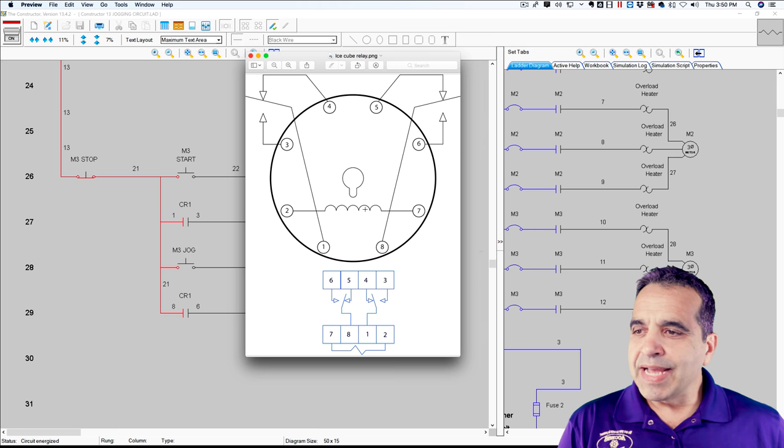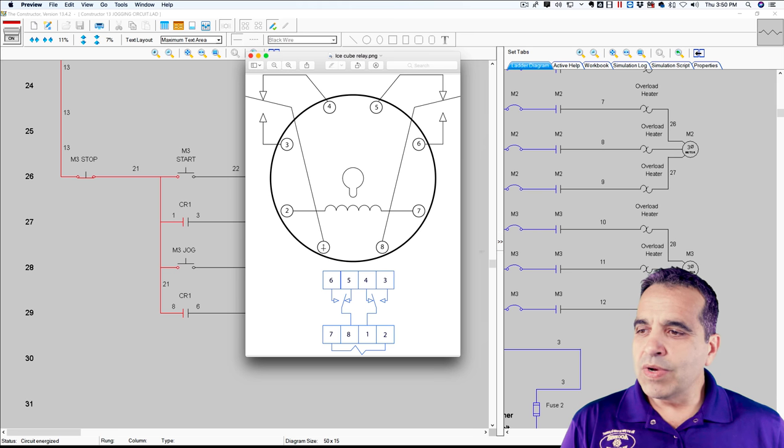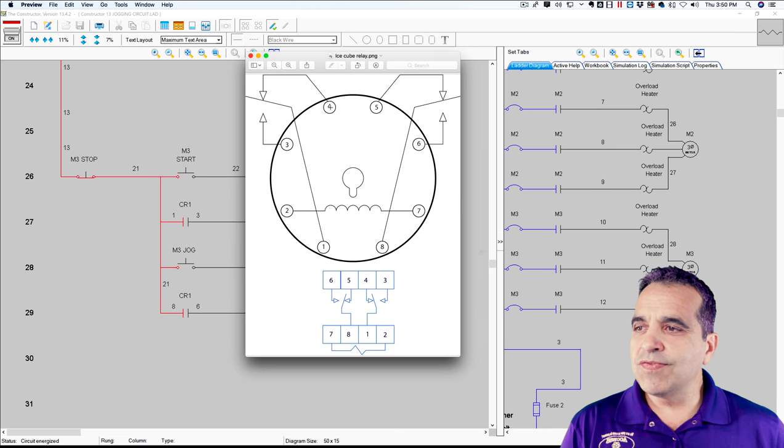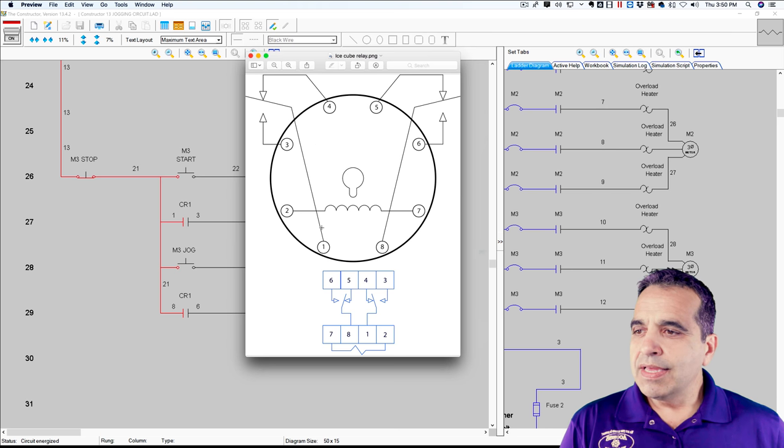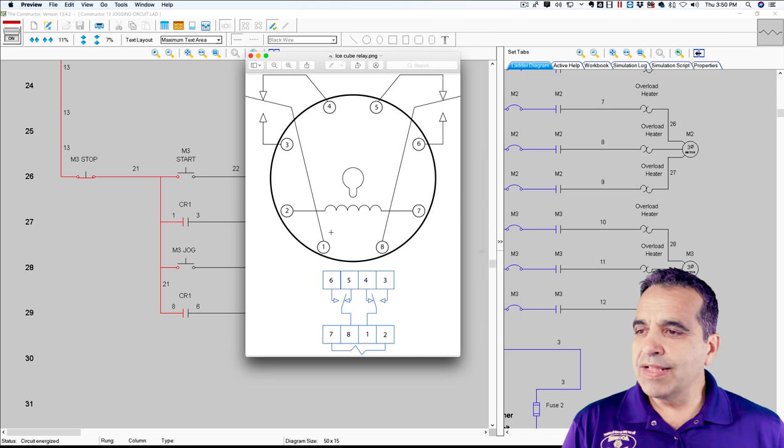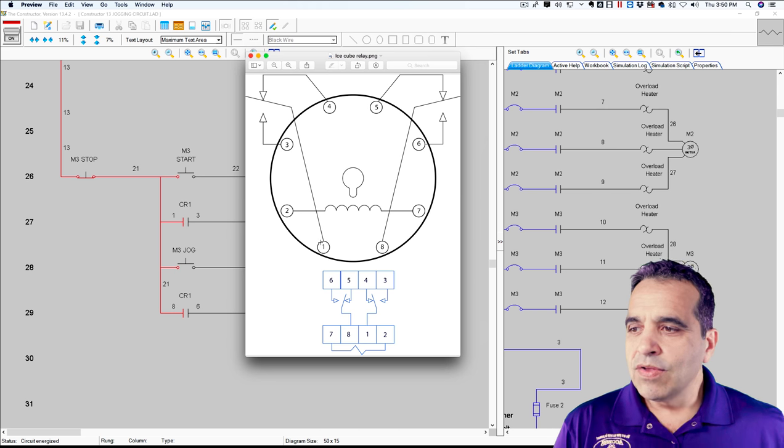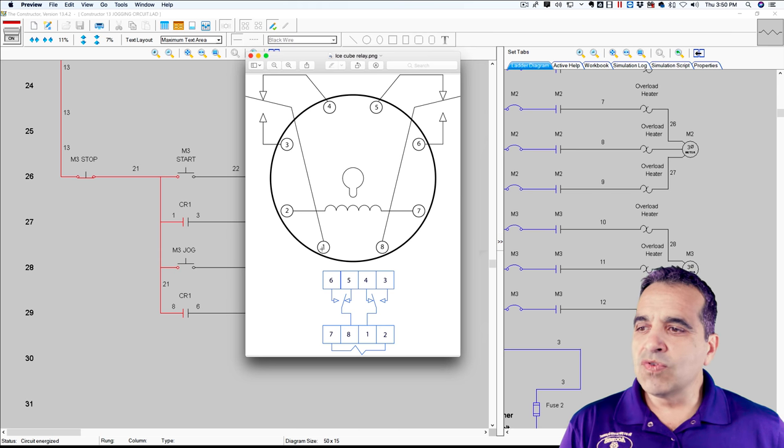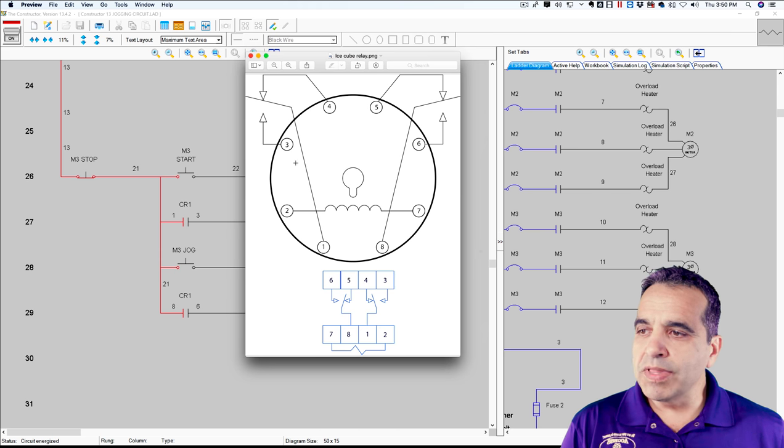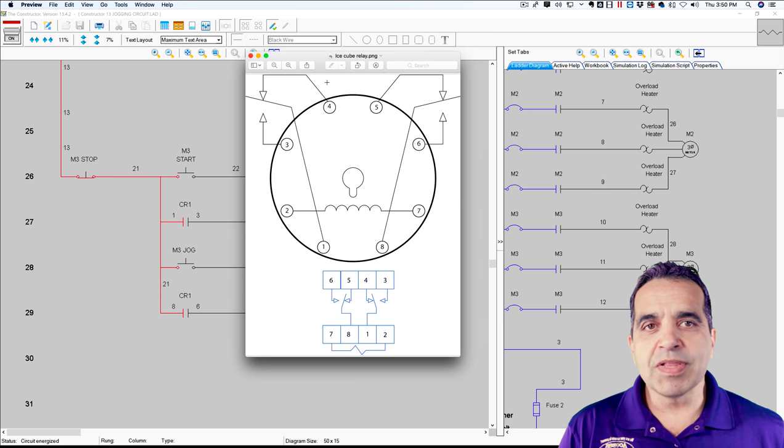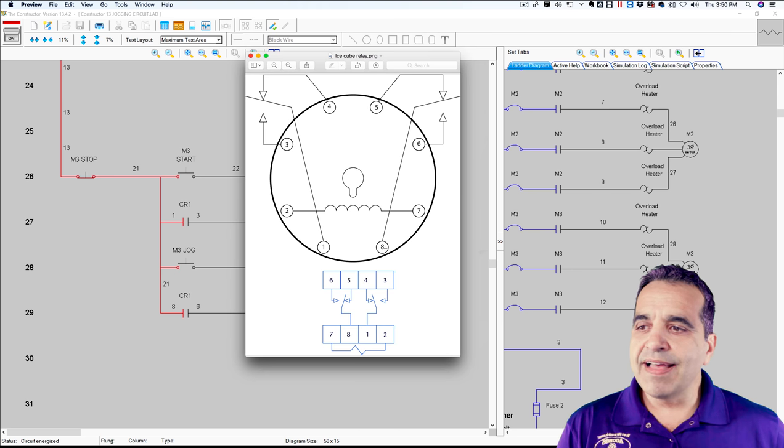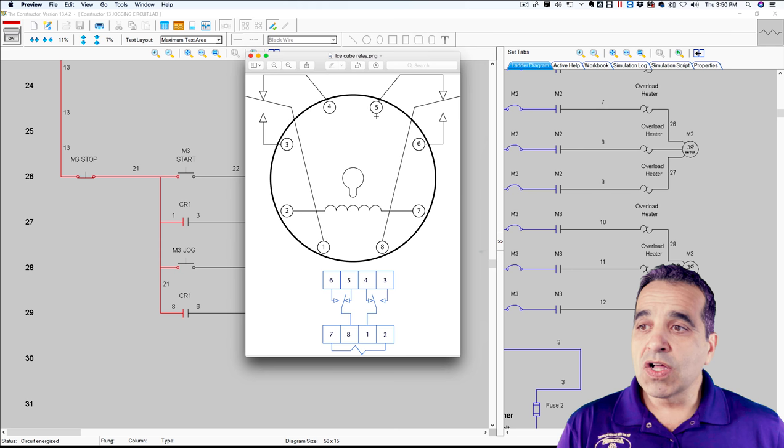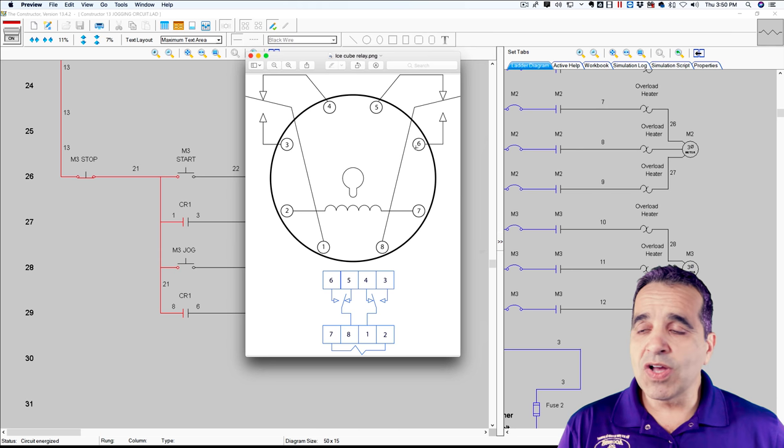And if you apply 110 volt between two and seven, a magnetic field will be induced. And right now circuit or whatever's on number one is connected to four. And once you apply voltage, this arm will move from four to three. And so one will be closed with three. So this circuit is normally open. One and three are normally open. One and four are normally closed. Same thing on this side. Eight and five are normally closed. Eight and six are normally open.